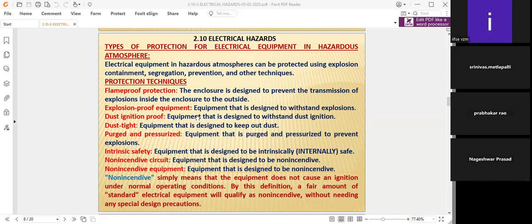The equipment that withstands flame, explosion, and dust ignition; dust-tight means equipment designed to keep dust out. The dust generated while the equipment is running, the dust extraction system must be running properly, so that there is no accumulation of dust on the equipment itself. Where process equipment is running near electrical equipment, and where dust-prone electrical equipment is there, we have to see that all the process departments and the maintenance departments keep the dust extraction working properly and in place.